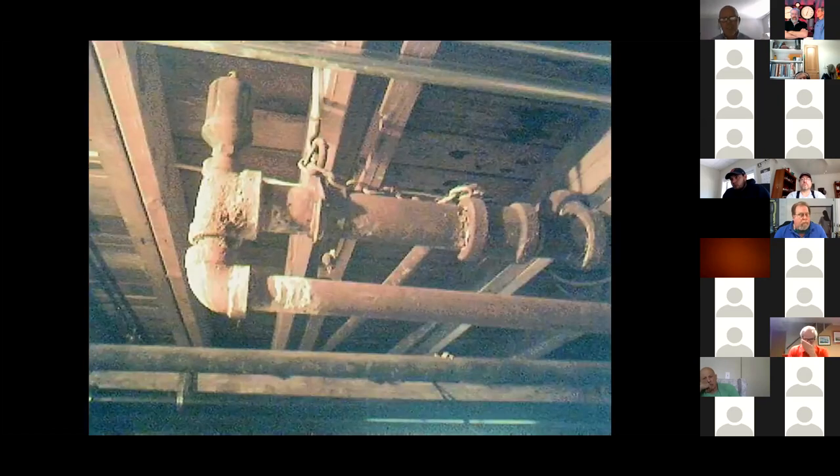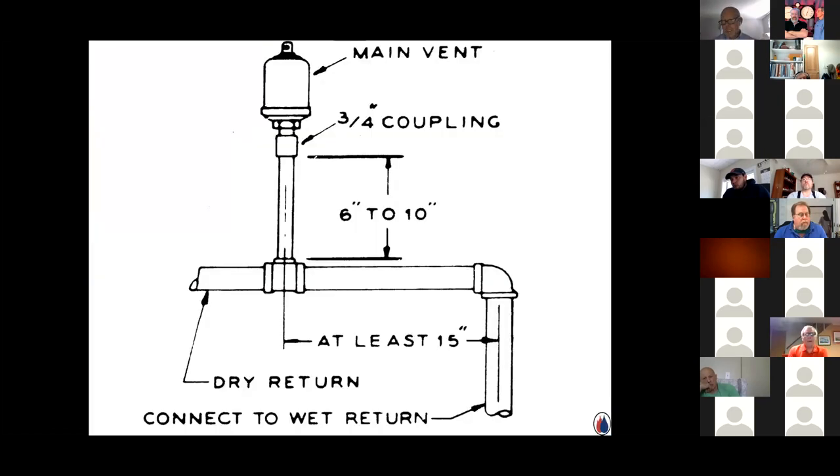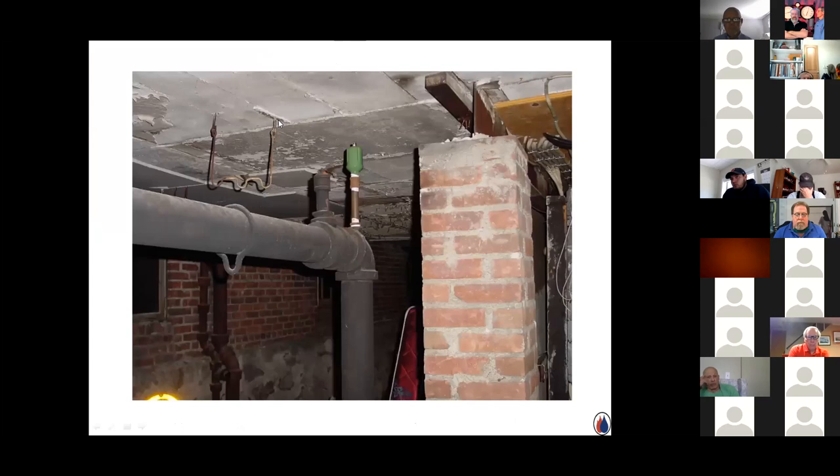Even when someone gives it an 'A for effort' and gets the vent up on a nipple, they could have taken advantage of the existing pipe to get it back further from the elbow as well. In the field you see low-capacity vents placed right at the end of the main on a T all over the place — both mistakes together. Moving on to two-pipe steam: when they first developed it, they made what was called a two-pipe air vent system, and we still find these all over downtown Boston — a supply valve on one side and a return valve on the other.